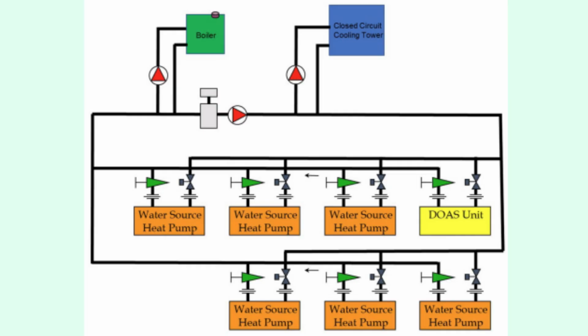Option 3. WSHP with built-in dehumidification and reheat. Some WSHPs now come with an internal reheat coil to remove moisture and warm the air before it enters the space. There are three types of reheat options. Hot gas reheat uses compressor discharge gas for reheat. It works, but it's complex and can be difficult to control consistently. Electric reheat, simpler, but comes with higher electrical demand and operating costs. Hot water reheat, the most efficient and reliable choice.